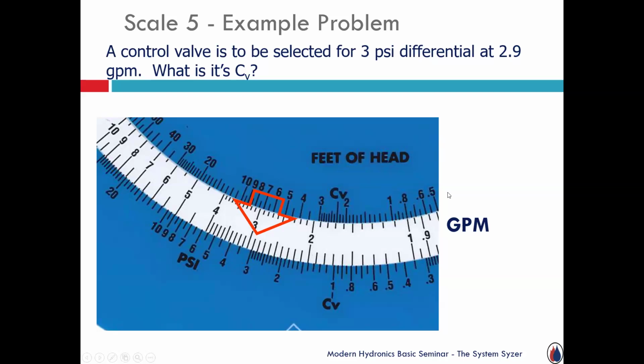Now, and you'll notice, and I mentioned it earlier, in scale 5, you have the letters CV. What are they lined up opposite? Well, on the bottom scale in PSI, it's lined up opposite the number 1 pound pressure drop. On the feet of head scale, it's the 2.3 feet of head. So they line up opposite each other. So what I want to do is, this is my known condition, 3 PSI pressure drop at a flow rate of 2.9. Read back. What CV should I be selecting? What flow rate in gallons per minute, because that's what this white band indicates, is the flow rate that will cause a 1 pound pressure drop, so that when I put it into a set of conditions where they want 3 pounds, this is the required flow rate.